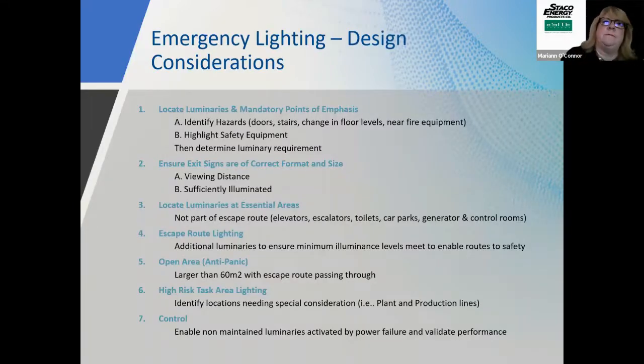When you're doing emergency lighting design, there's a lot of design considerations that you need to take into account. So let's say points of emphasis. Those are mandatory points of emphasis. So doors, stairs, are there changes in floor levels? Are you near fire equipment? So you're looking at what your lighting requirements are, what your loads are, and where the lighting has to be. For example, if you're having an exit sign, what is the viewing distance? Is it sufficiently illuminated? You have to look and say, hey, we have an escape route. What is that escape route? And how much does the lighting have to be illuminated there?